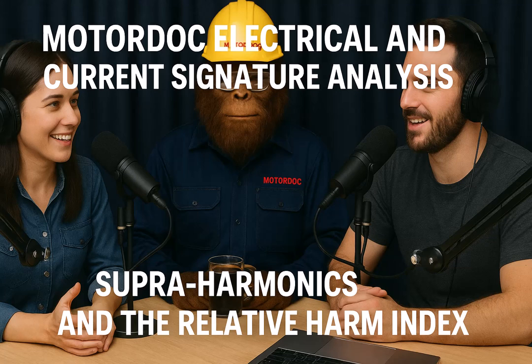So this lets us reliably compare data taken at different times, different operating conditions. It's like having a consistent yardstick for machine health, regardless of how hard it's working at that moment. Makes sense. And finally, for the basics, knowing the machine's speed seems crucial. Oh, absolutely critical. You need the running speed and the pole pass frequency, PPF. It's mathematically tied to the motor's poles and its operating slip. Identifying these is key because mechanical characteristics create specific peaks in the spectra. Trained analysts know what to look for.